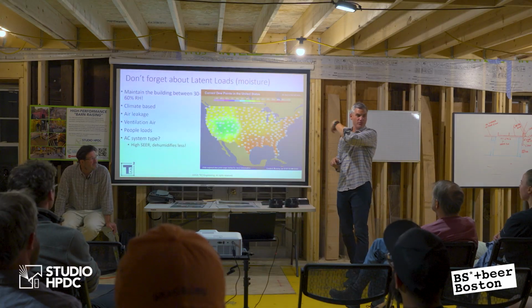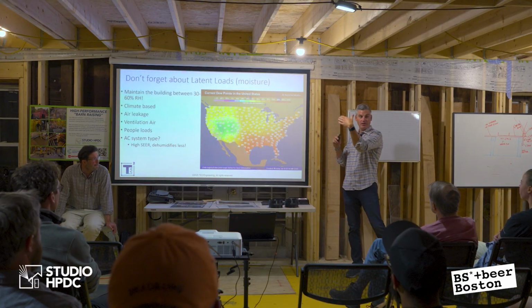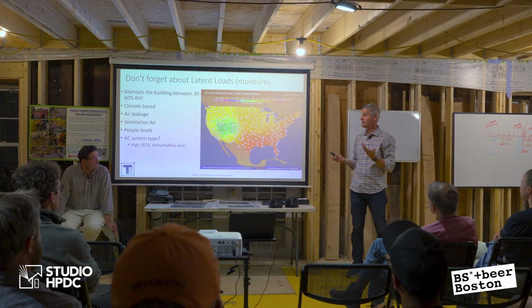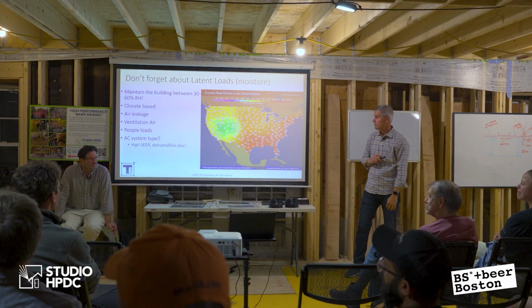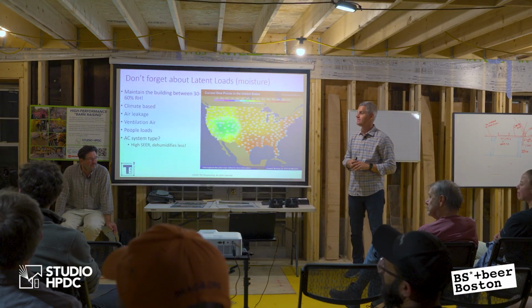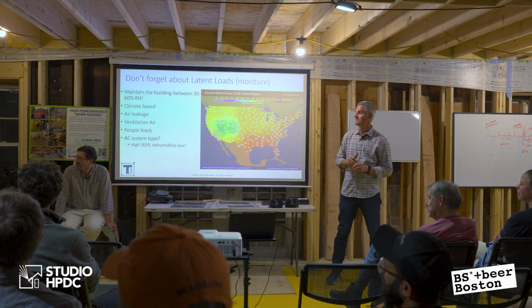Yeah, back to that total external static pressure graph I was showing you. Each of those components matters. You've got to get its size right. You've got to budget for your static. Don't blow it all on the smallest coil to save $100 on a coil.